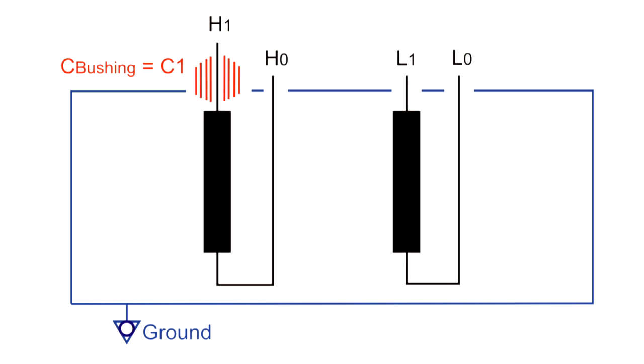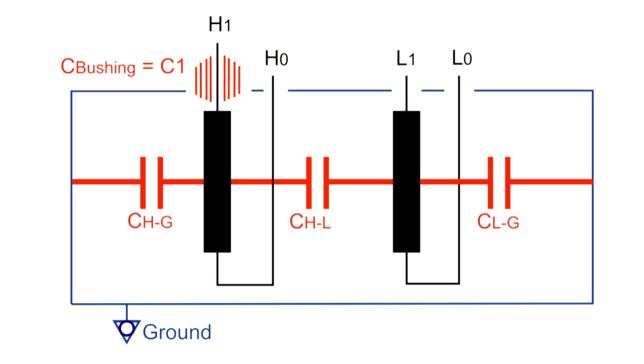There are three measurable capacitances: the one from the high voltage winding to the core, the one between the windings, and the one from the low voltage winding to the tank.